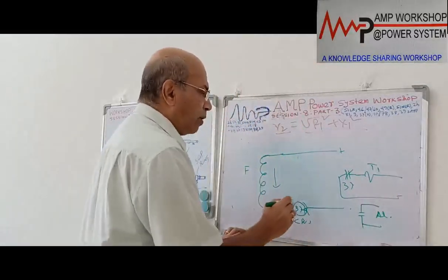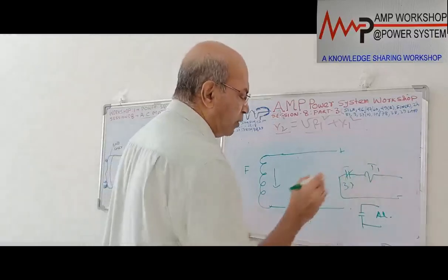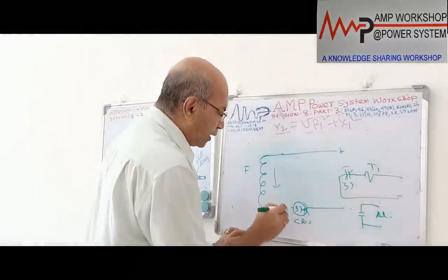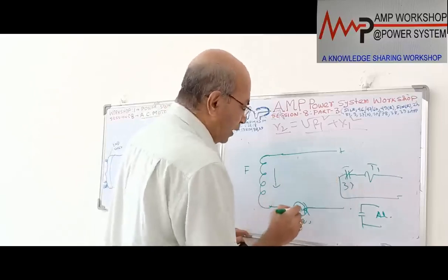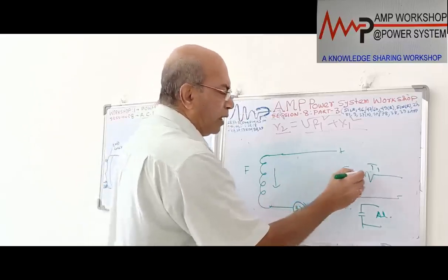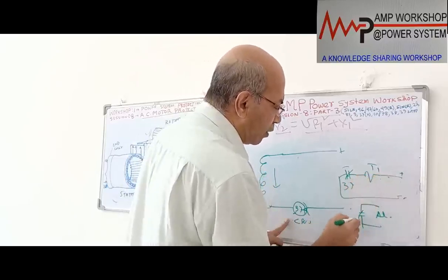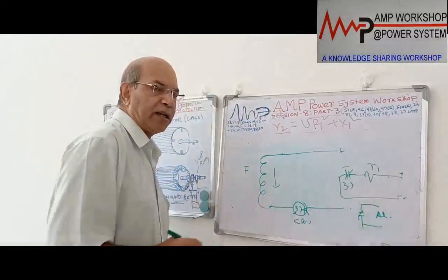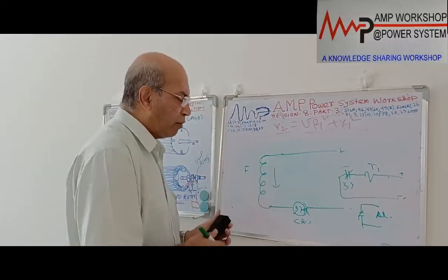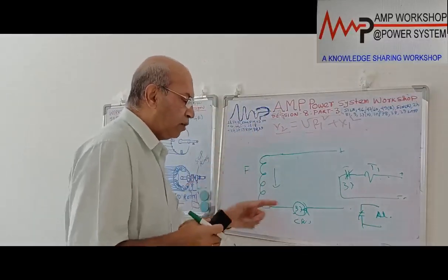In that case, what will happen? Normally this relay is picked up, so this contact is open and the timer is not energized. The moment the current drops to 80%, this relay will drop out, the contact will become NC, and T1 will pick up. The moment T1 is picked up, this contact will close, and we will get an alarm or we can get the trip of this motor.